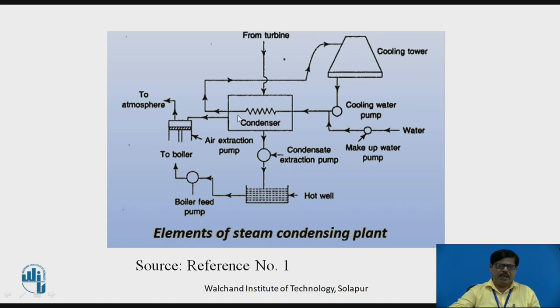The function of the air extraction pump is that whenever steam enters the condenser, dissolved air also enters along with the steam. There are also other sources of leakage — air may leak through joints, etc. This air has to be continuously removed with the help of the air extraction pump; otherwise it will increase the pressure in the condenser and condensation will not take place properly. So, the air extraction pump is used to maintain the required vacuum inside the condenser.